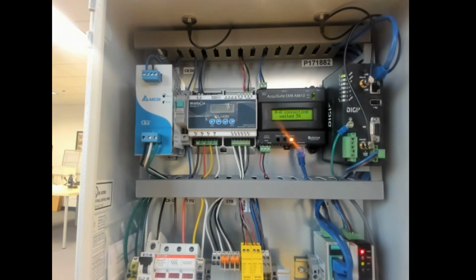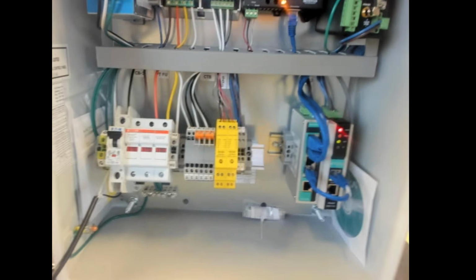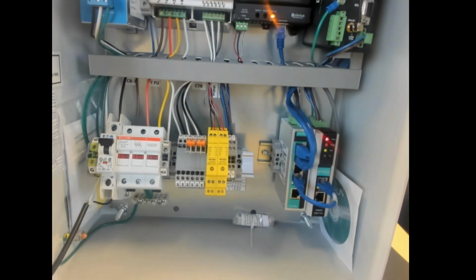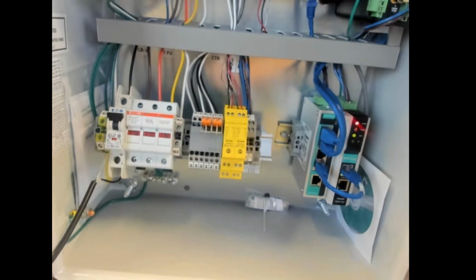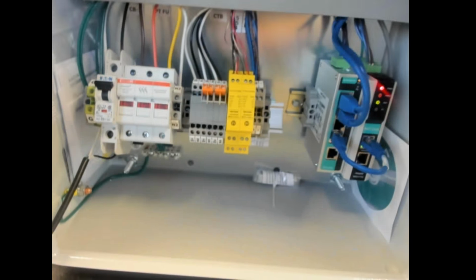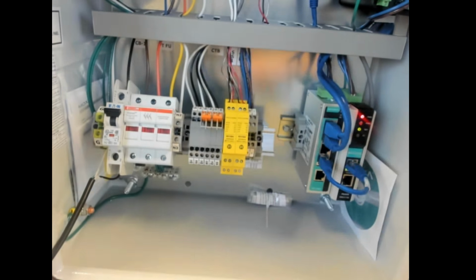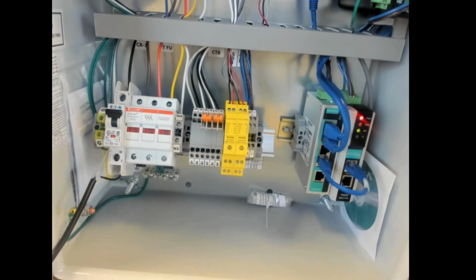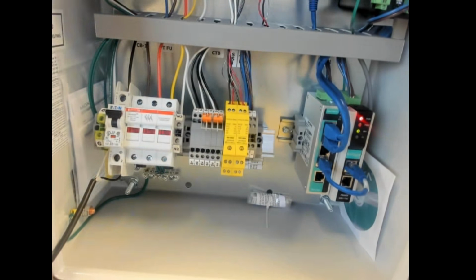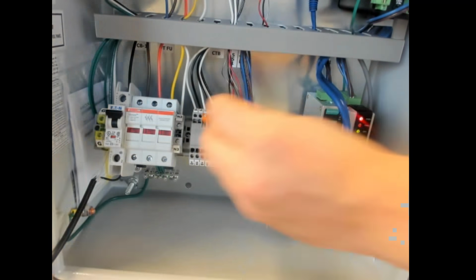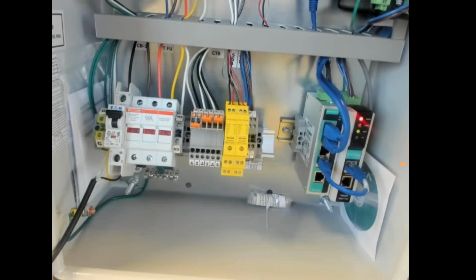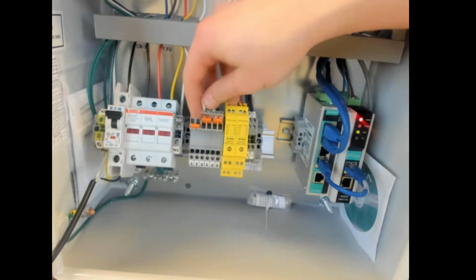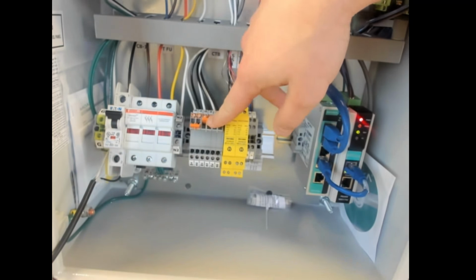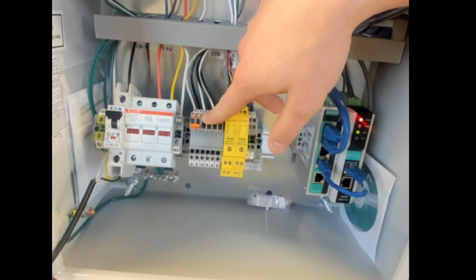The other difference with 5 amp CTs is that because it's a lot more current and a lot more dangerous, there are some additional protections in place. You'll notice at the bottom here in the terminal block we have a few of these orange tabs - that's called a shorting tab. It's a little bit of a complex mechanism, but it's not that hard once you work with it.